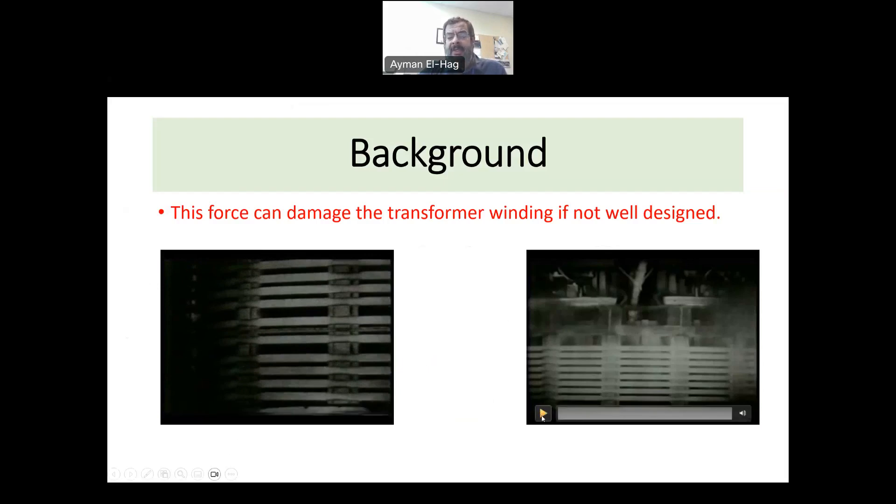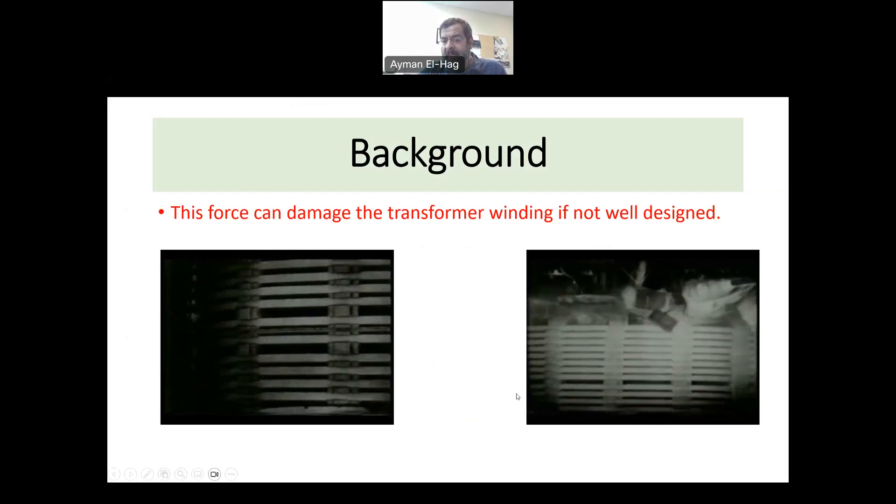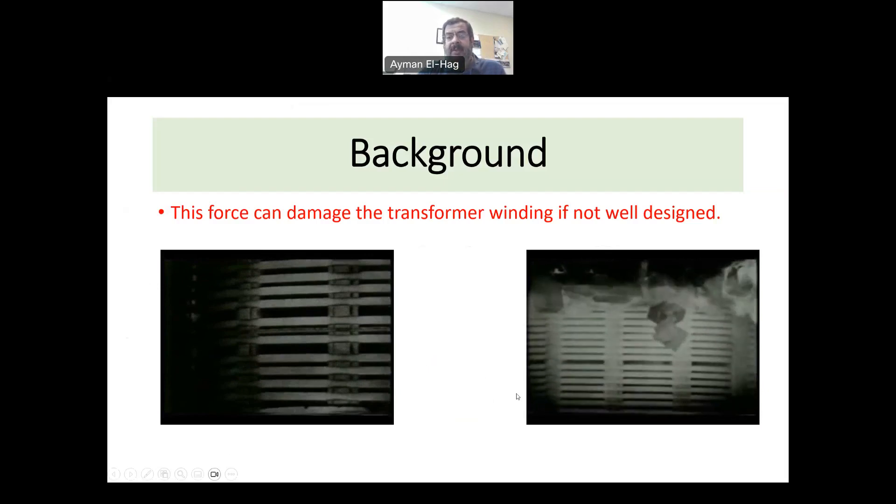Now, if the transformer is not properly designed, something like this. We see a mechanical failure in the windings because the transformer winding is not well designed to handle such short circuit.